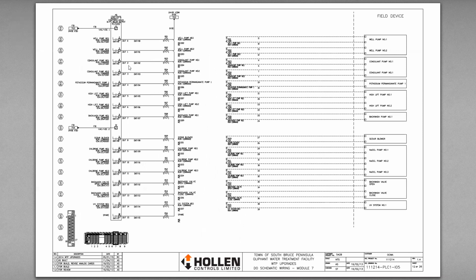This particular panel uses what are called interposing relays. So we have a 1769 OW16 that is wired up to 24 volt control relays, and then the contacts of those relays. You can see here that the normally open contact of RO1 is well pump number 1. It just says well pump number 1. I'm assuming that's run command. So the normally open contact of this control relay, well pump number 2 run command, coagulant run command, potassium permanganate, high lifts, backwash pumps, scour blower run command, NaOCl pump, sodium.